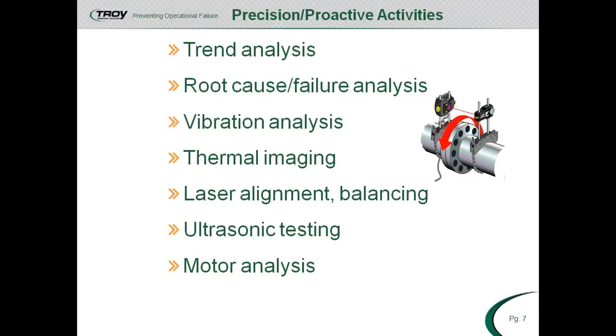It can look at the fault zone of the air gap. The air gap fault zone describes the measurable distance between the rotor and the stator within the motor. If this distance isn't equal throughout the entire circumference, air gap eccentricity occurs. That varying magnetic flux is measurable, and the analyzer will see it. The software package will flag it and record it and give you an alarm. And this condition can cause harm, and it can actually cause a dangerous condition within a motor.